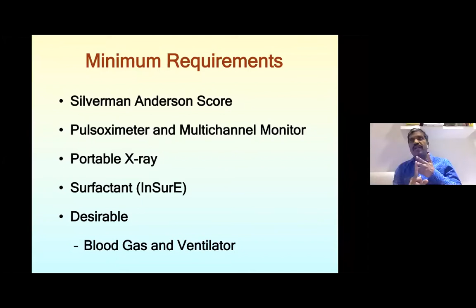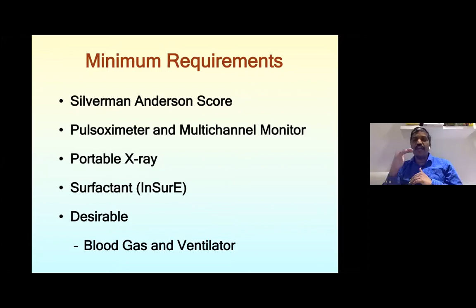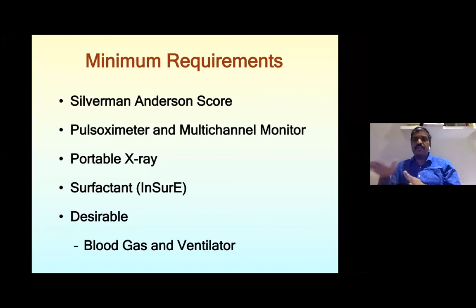So what is low, what is normal, and what is high lung volume? Low is when your intercostal spaces are less than 6 spaces. Normal is when your intercostal spaces are 6 to 8 spaces. High volume is when your intercostal spaces are more than 8 spaces. More than 8 spaces, you have to decrease the pressure. 6 to 8 spaces, your pressures could be normal. That means there is no need to change your CPAP pressure. If your volume is low, that means your intercostal spaces are less than 6, then you have to increase your CPAP pressure. So the two methods of changing pressure are, one, saturation, and second, X-ray.